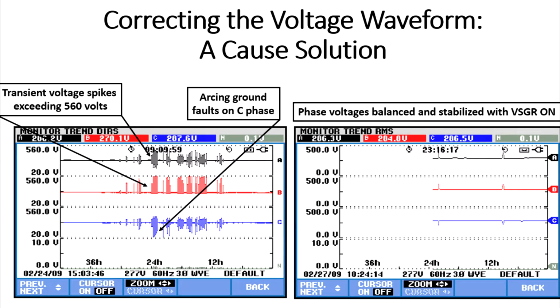When people talk about voltage spikes and arcing grounds and all of this stuff, it's just words unless you can actually see it. Here's a brief power study that was done showing many variations in the voltage. You'll see the smooth black, red, and blue lines going along. And what was going on in the middle here is there were transient voltage spikes exceeding the peak voltage significantly. They were exceeding 560 volts. There were hundreds of them over a 24 or 30-hour period. Each of them, or many of them, were causing the computer-controlled process to stop. The computer would have to be powered down and then powered back up, and the whole process restarted again. Most process control, it's very expensive every time they have to do that.